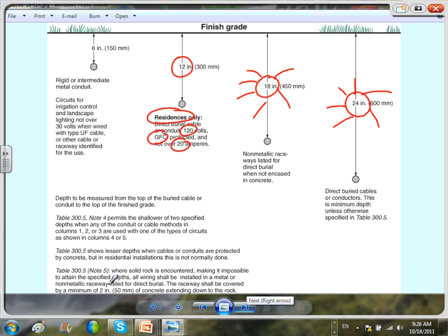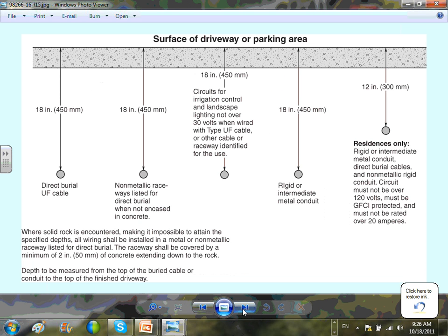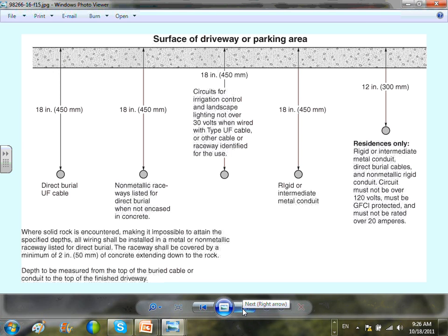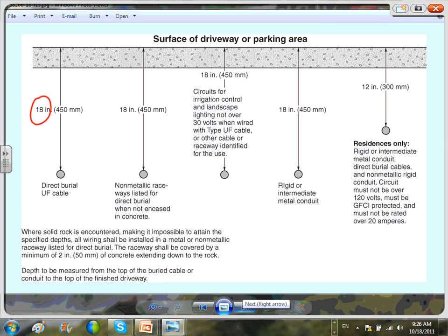Okay. This one is really interesting. If it's a rocky place, guys, they allow you to put conduits and bury them with 2 inches of concrete. We'll talk about this table more as we go to the commercial too. Look at this, surface or driveway or parking areas. If your situation is under a surface or a parking area, look at that, direct buried cable, they lower it a little bit to 18. Can you guys see that?